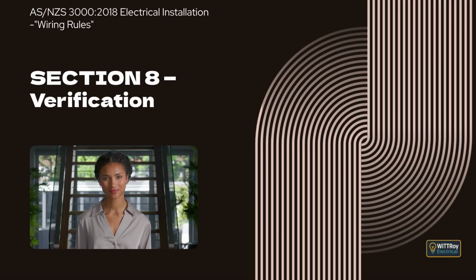Clause 8.3.9 Verification of earth fault loop impedance, spoken as EFLI. This clause explains the requirements for verifying earth fault loop impedance. The purpose of EFLI verification is to confirm that, if an earth fault occurs, the fault current will be high enough to cause the protective device to disconnect the supply within the required time.